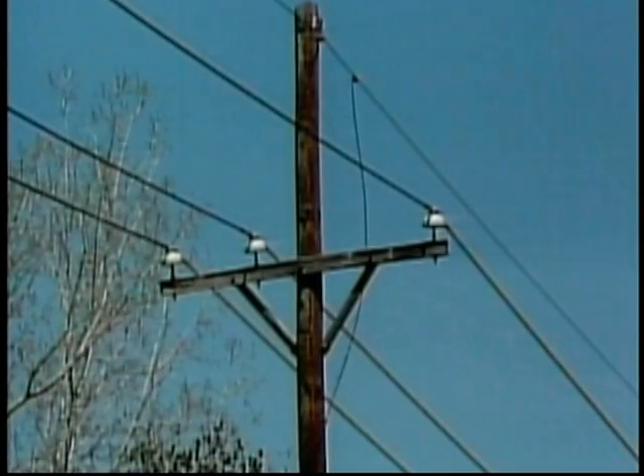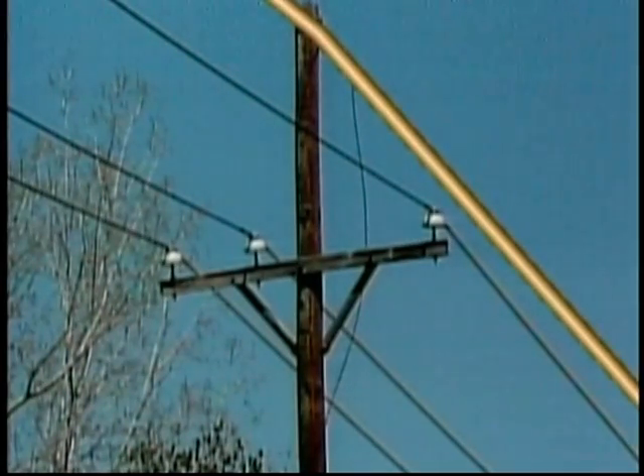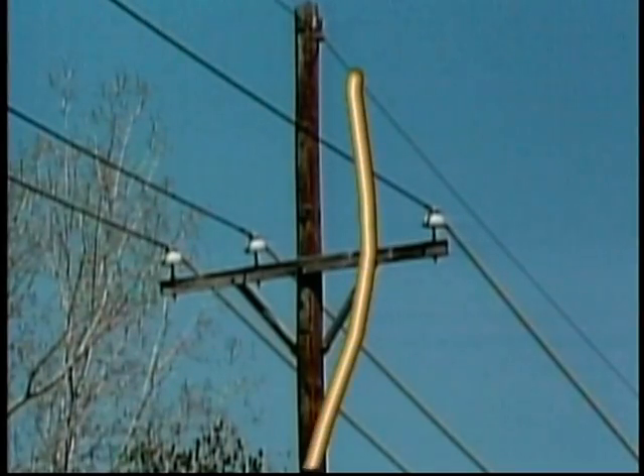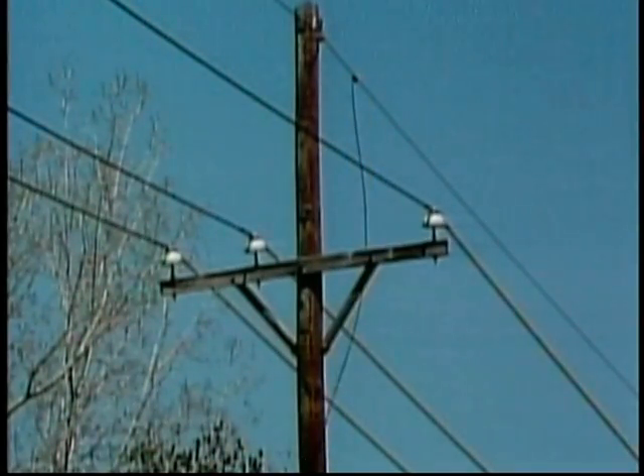A static wire may be used in place of or in conjunction with surge arresters to help protect equipment and lines from lightning strikes. A static wire is a wire that runs along the top of distribution poles. It's connected to ground wires that run down the poles to ground. The static wire provides a cone of protection from lightning strikes for the distribution lines below it.